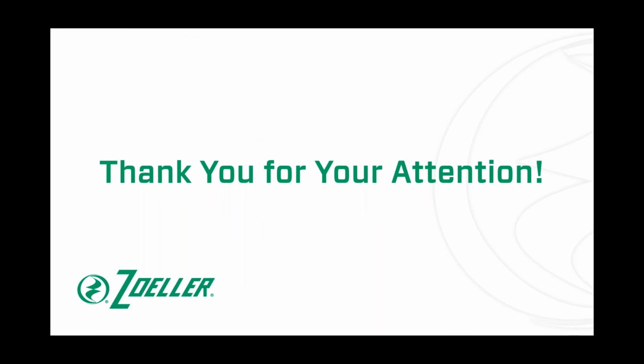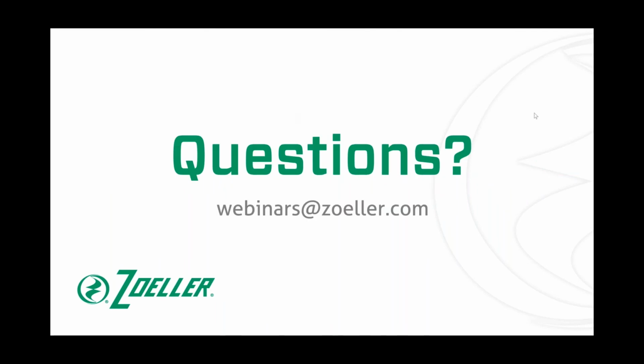I hope this has been informative, and I hope you've learned a little something from it. Again, I hope it's been beneficial to you. There are some attachments here on this webinar, so please look. You'll see I've attached a Zoeller startup sheet, and another sheet that explains all of the boxes of the startup report in detail, with some troubleshooting on some of them. The last thing I attached was a basin or tank capacity chart. This is something you can carry with you, and when you're out in the field and need to figure out how many gallons a particular pit or basin might hold, you can use this chart to figure out exactly how many gallons per inch the tank or basin has. So when you do that functional drawdown test, you'll know exactly how many gallons per minute you got rid of.